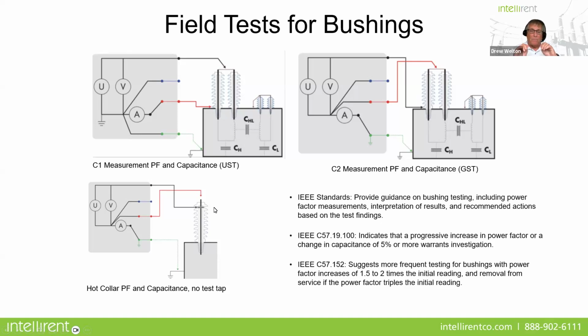The best guidance on how we're going to perform these tests is available through certain IEEE standards. C57.19.100 indicates that a progressive increase in power factor or change in capacitance of 5% or more warrants investigation. Now, I didn't say change it out or take it out of service, just more investigation. C57.152 suggests more frequent testing for bushings with power factor increases of 1.5 to 2 times the initial reading, and removal from service if it triples the initial reading.